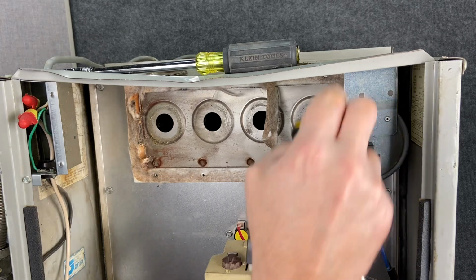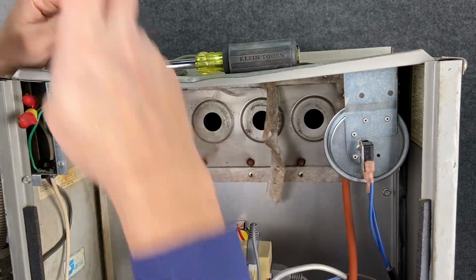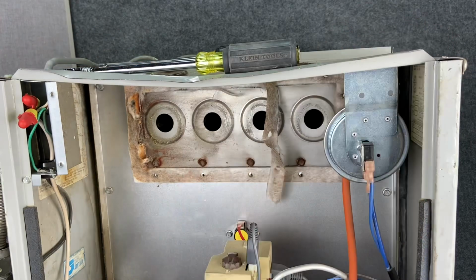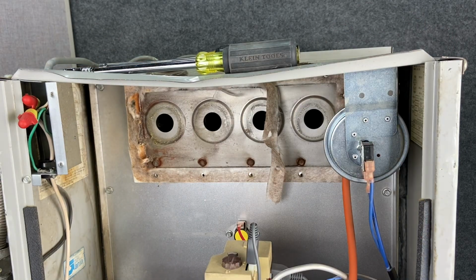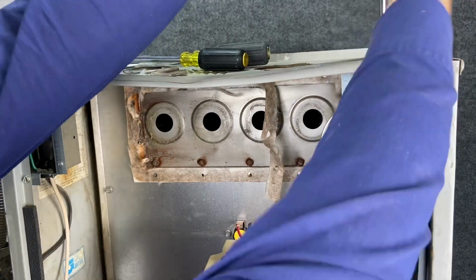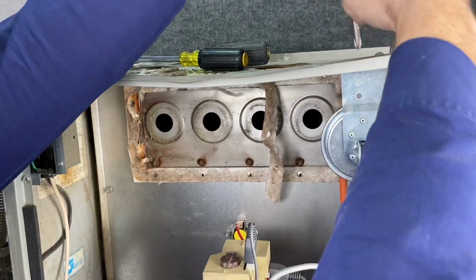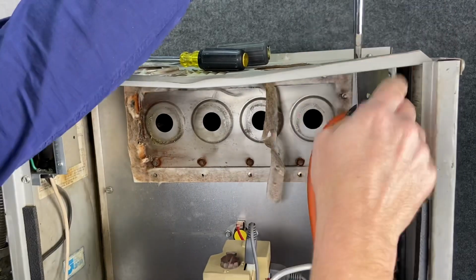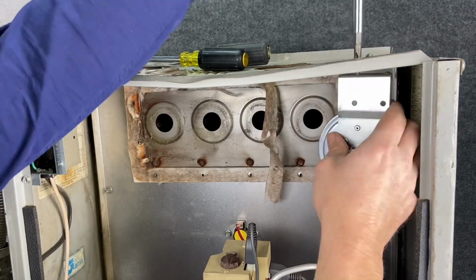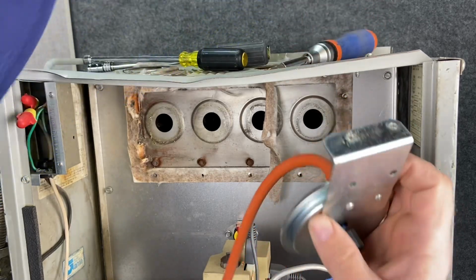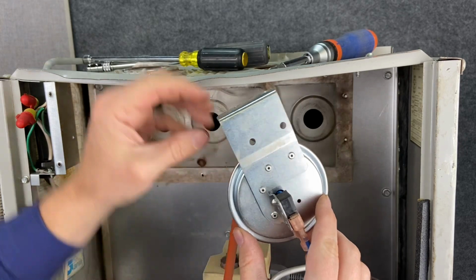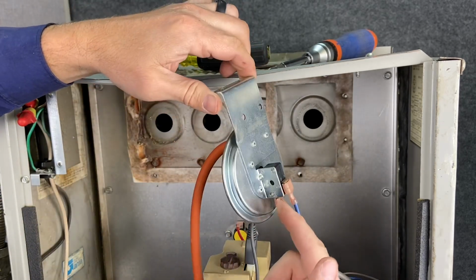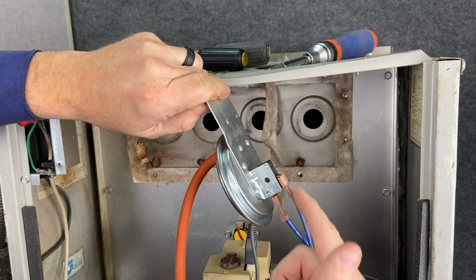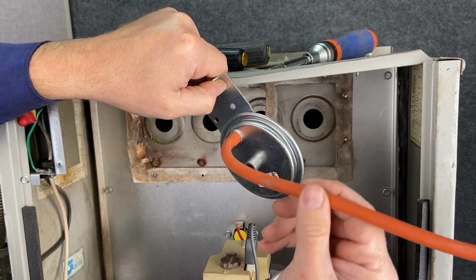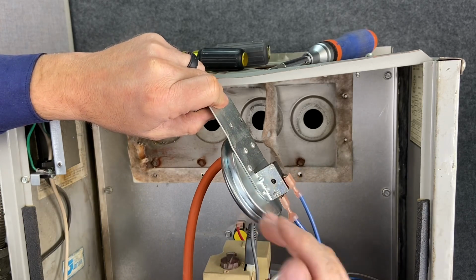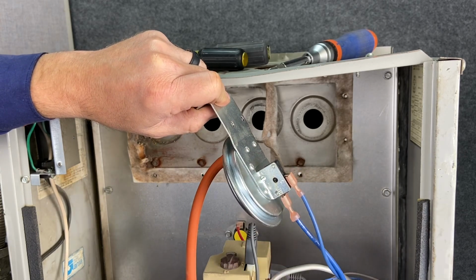As we continue on our path of destruction of this furnace, we're going to look at our pressure switch specifically, and this uses a Phillips screwdriver at the top. So this is our pressure switch. It's very simple, it's just a micro switch here. It's NO, normally open. So we have our 24 volts coming here. When we pull a vacuum to this switch, the diaphragm pulls the switch closed, and this wire connects that wire. 24 volts returns to the IFC.